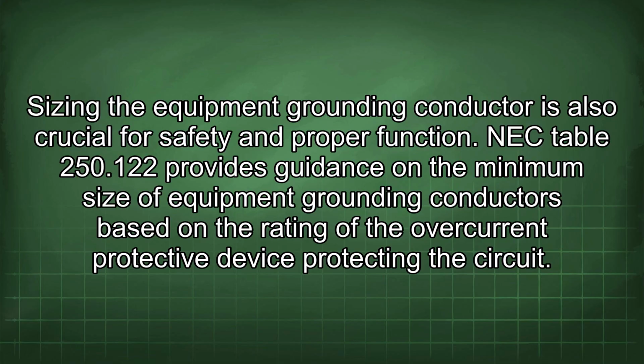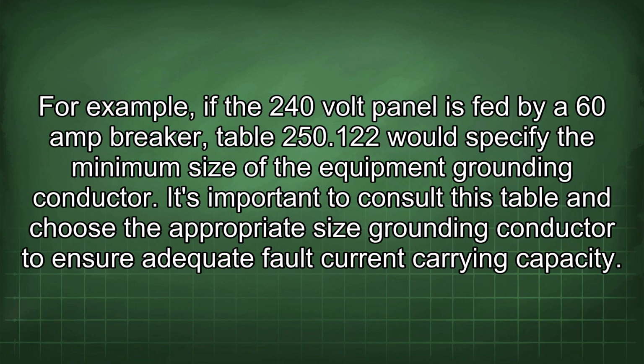250.122 provides guidance on the minimum size of equipment grounding conductors based on the rating of the overcurrent protective device protecting the circuit. For example, if the 240-volt panel is fed by a 60-amp breaker, Table 250.122 would specify the minimum size of the equipment grounding conductor. It's important to consult this table and choose the appropriate size grounding conductor to ensure adequate fault current carrying capacity.